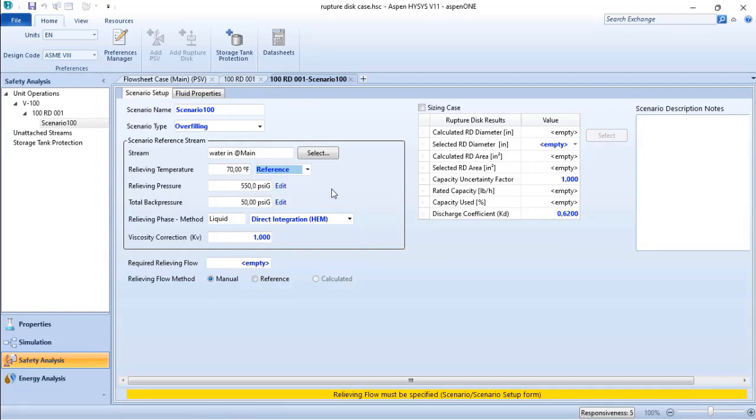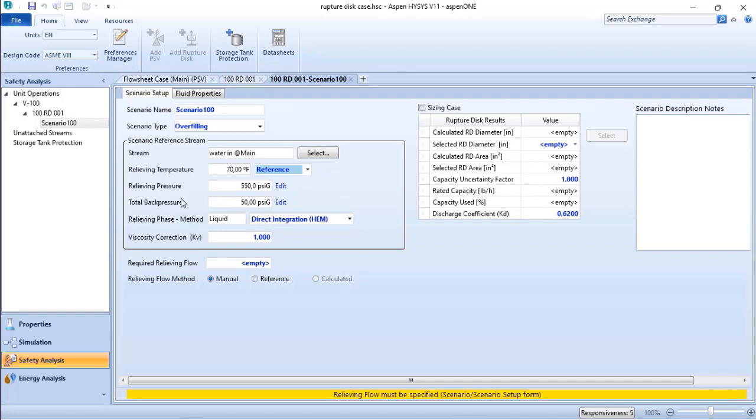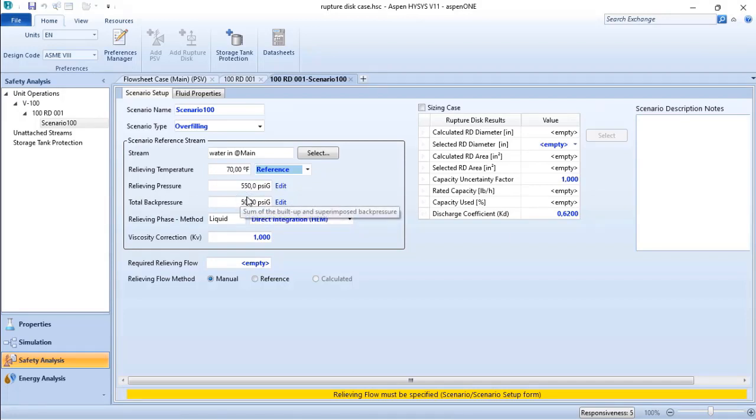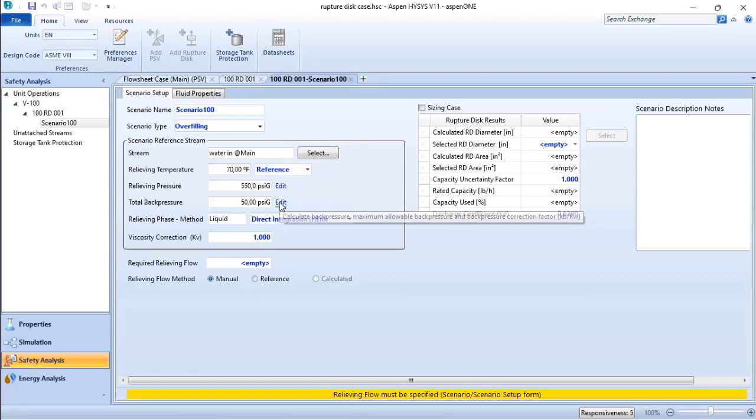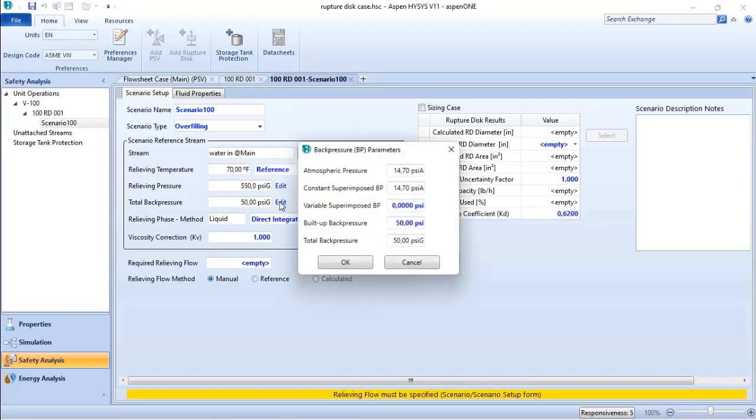because based on API 520, I have an allowable relief pressure of 110% of the maximum allowable working pressure. My total back pressure is not 10% of the relief pressure; I have that informed in my design.